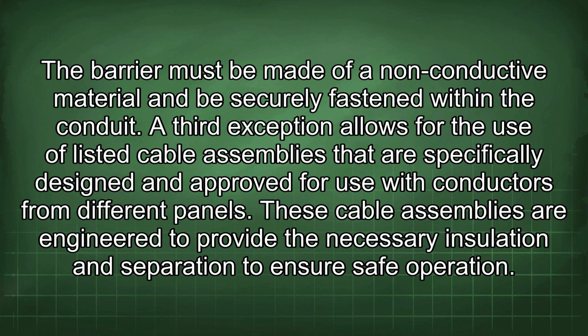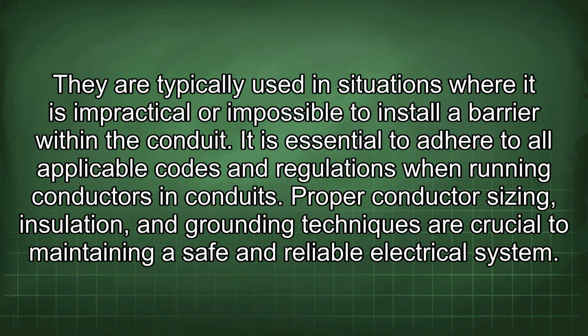A third exception allows for the use of listed cable assemblies that are specifically designed and approved for use with conductors from different panels. These cable assemblies are engineered to provide the necessary insulation and separation to ensure safe operation. They are typically used in situations where it is impractical or impossible to install a barrier within the conduit. It is essential to adhere to all applicable codes and regulations when running conductors in conduits. Proper conductor sizing, insulation, and grounding techniques are crucial to maintaining a safe and reliable electrical system.